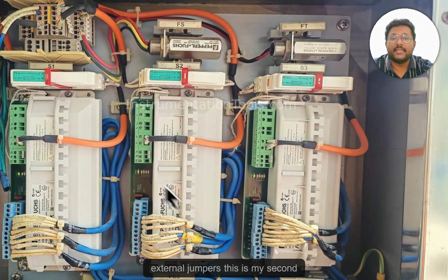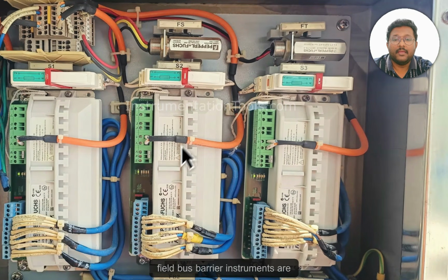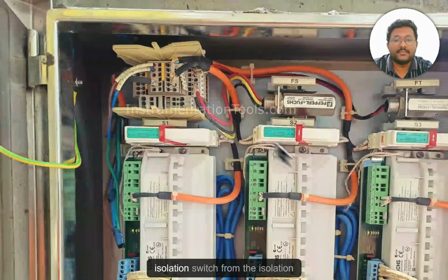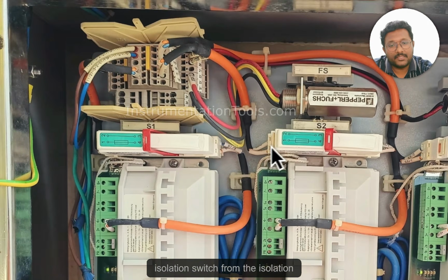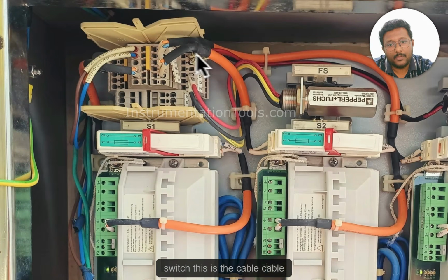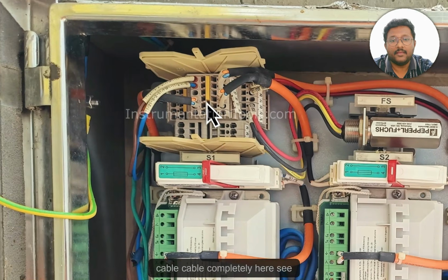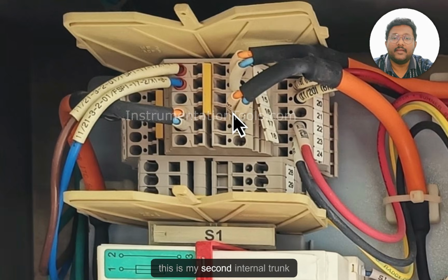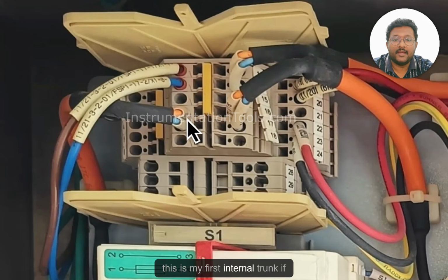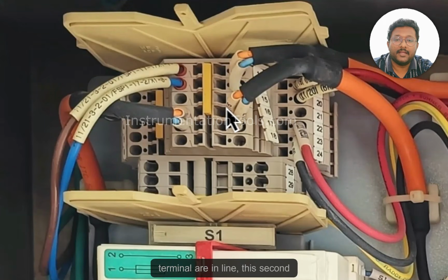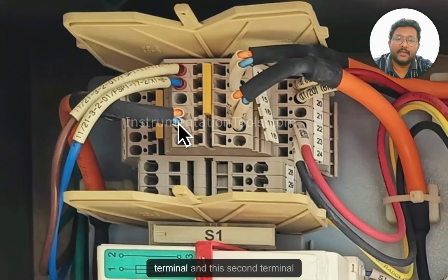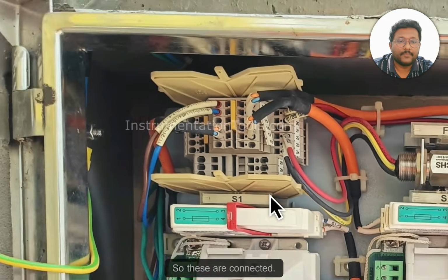This is my second field bus barrier. Instruments are connected here. Internal trunk. Again, isolation switch. From the isolation switch, this is the cable connected here. See, this is my second internal trunk. This is my first internal trunk. If you see, this first terminal and this terminal are in line. This second terminal and this second terminal are in line. So these are connected.